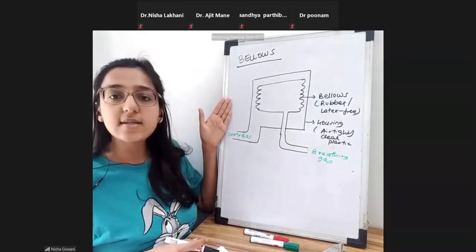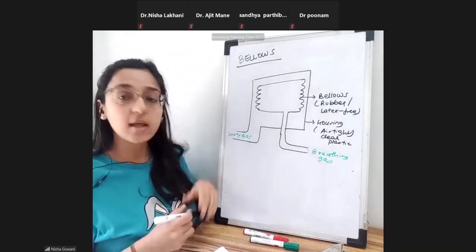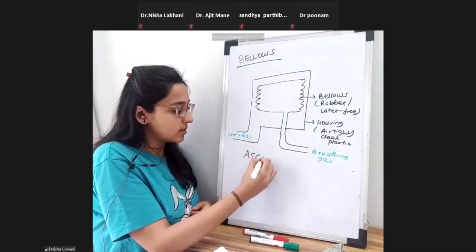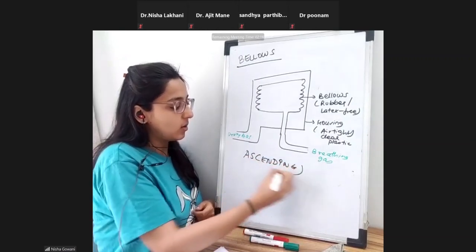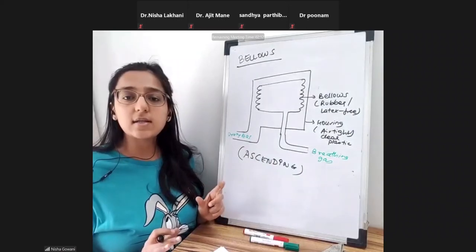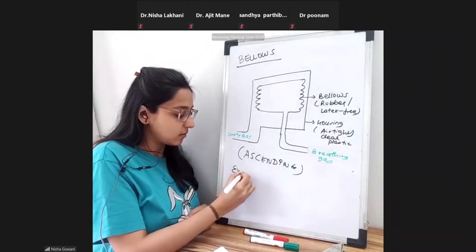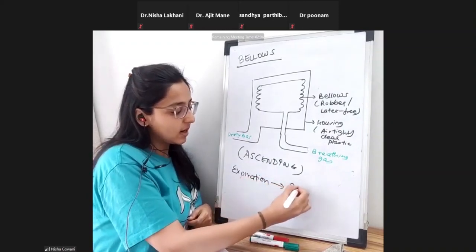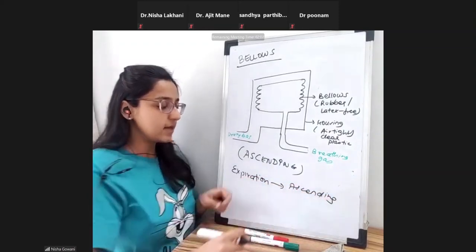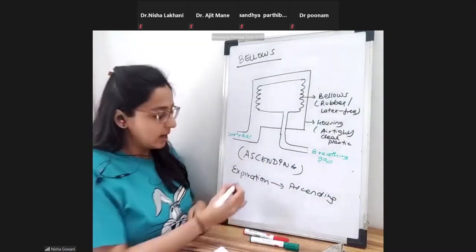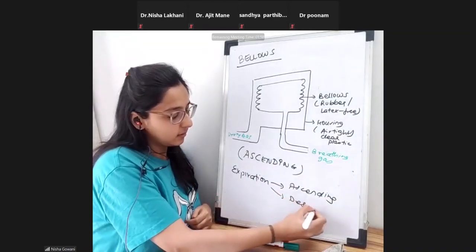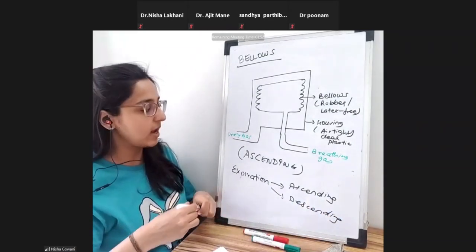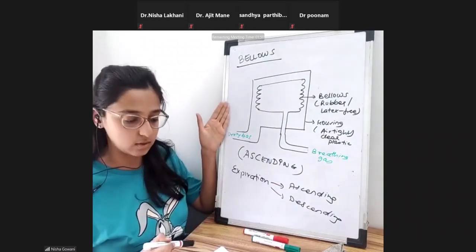This is how the bellows assembly looks. Bellows can be ascending type or descending type. What I have drawn here is the ascending type. What determines ascending or descending is the expiration — if the bellows are ascending during expiration, they are known as ascending type. If during expiration they are descending, they are the descending type.